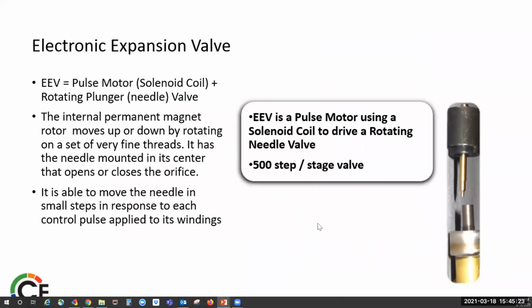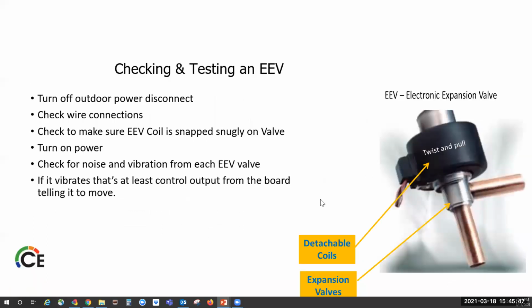All right, now we're going to get into the other components like the electronic expansion valve. The electronic expansion valve is controlled by algorithms in the board. So basically, it's its own computer, and it's designed to work at variable speed capacities with little needles. And in this case, this particular one is a 500-step staging valve. The coil can be replaced without changing out the valve. If it isn't acting properly and you suspect the expansion valve, make sure this is connected tight and it's not loose and vibrating around.